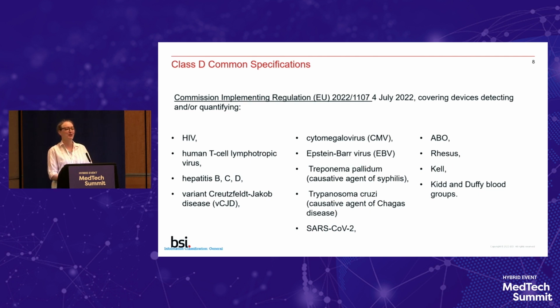So what you need to do when you read the common specifications is work out which annex applies to your device, and then work out which table within that annex applies to your device. Once you've worked that out, they're actually really helpful for design and manufacture. They're also really helpful for notified bodies to review. We have a checklist, and it's a matter of tick, tick, tick. Does the manufacturer meet these requirements, or do they not?